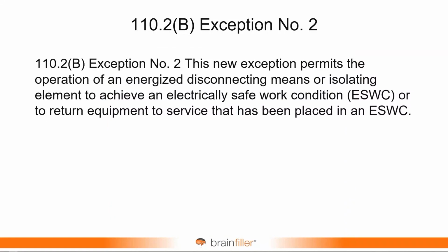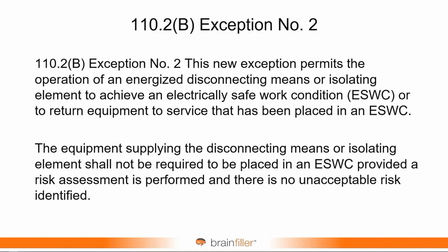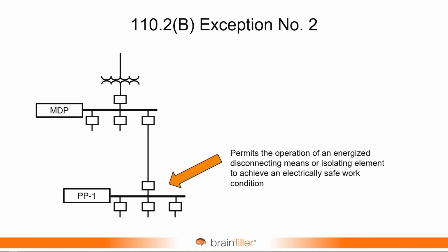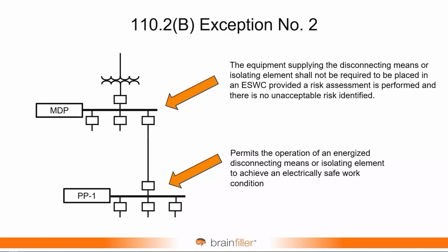There's another exception that permits the operation of an energized disconnecting means to establish an electrically safe work condition and return it to service as well. And the equipment supplying that disconnecting means or isolating element is not required to be placed into an electrically safe work condition. It's just a little bit of a clarification. So if you operate this device down here to establish an electrically safe work condition, it simply means you don't have to do it up here as well.